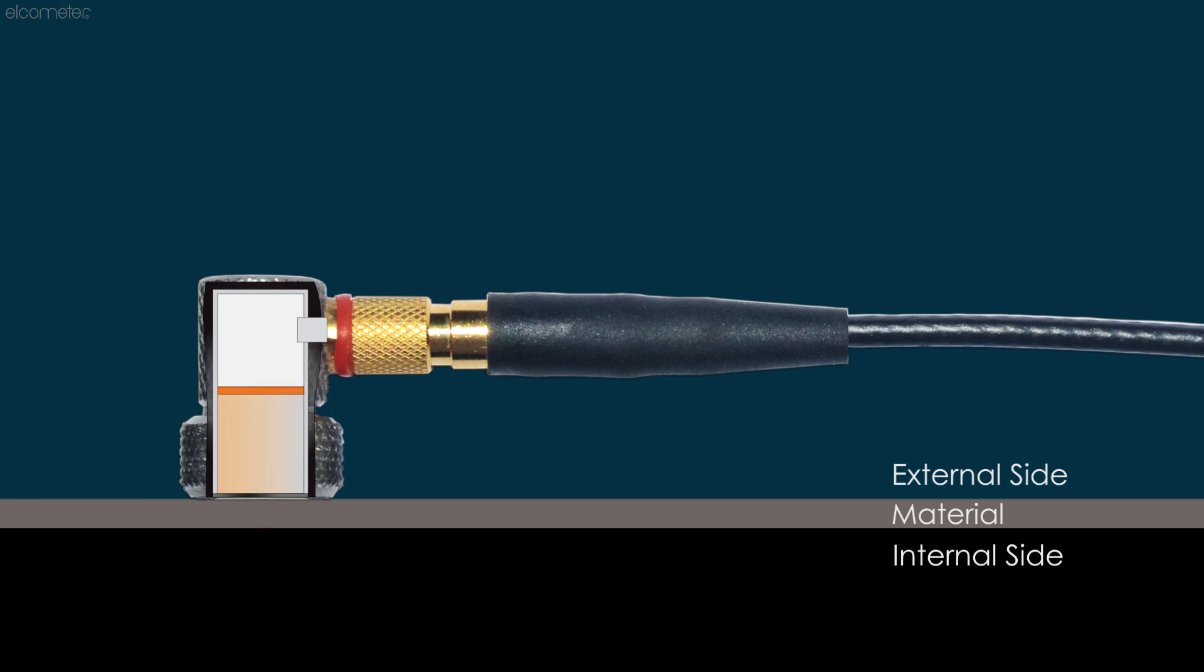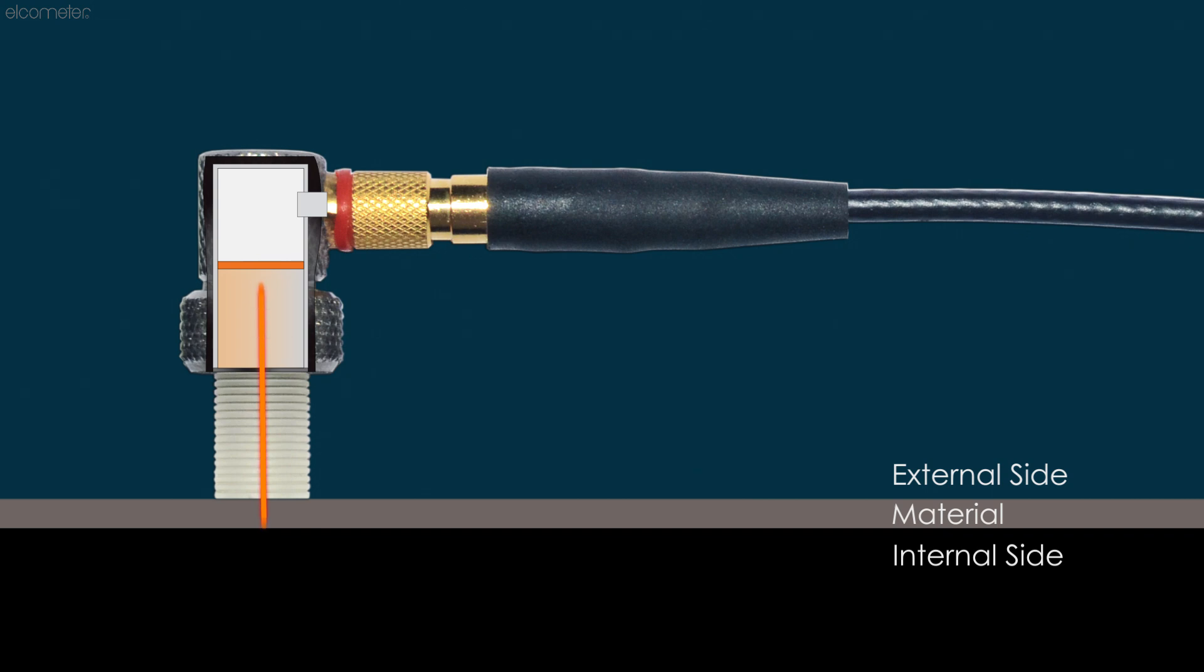...single element transducers use a delay line to increase the time between the pulse being sent and the echo being received, ensuring more accurate results.